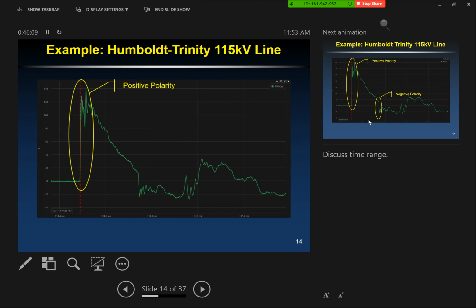So what's our next point of interest? You'll use your traditional fault location techniques to point you to where you should be looking. For this one, it pointed us right here, which looks like a significant event, and we note a negative polarity step change. So is this a local reflection or a remote reflection? It's off the remote end.